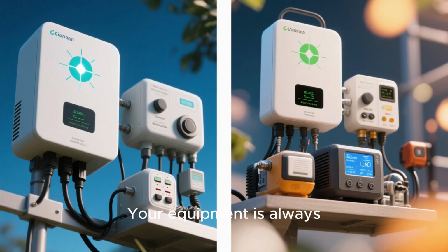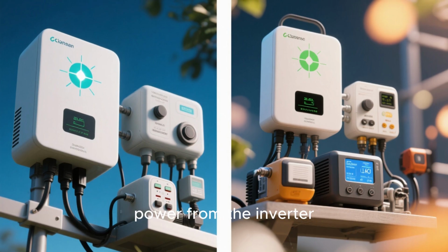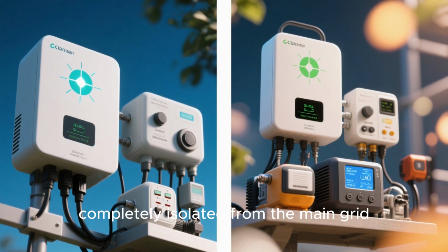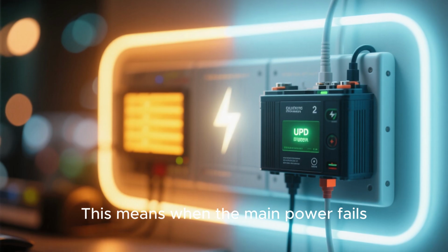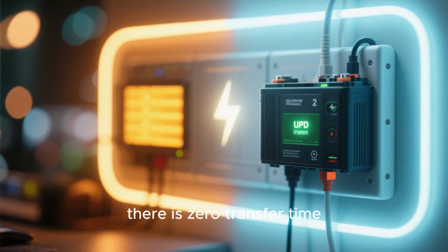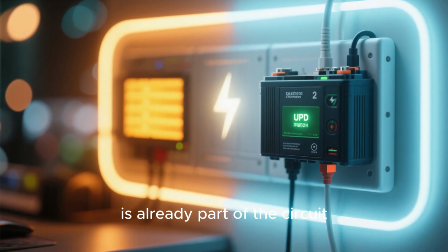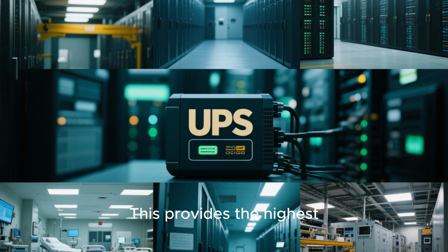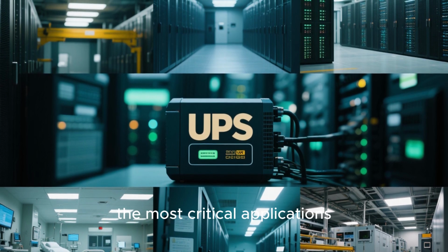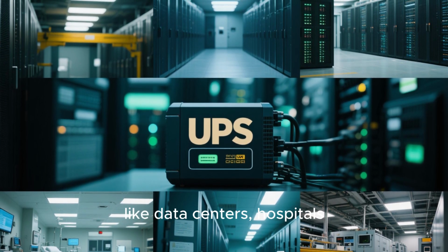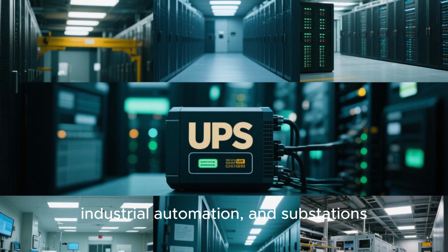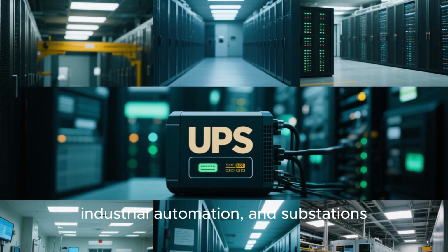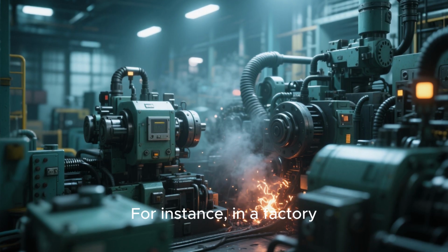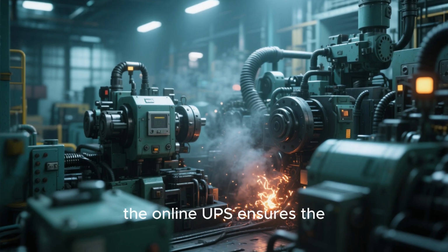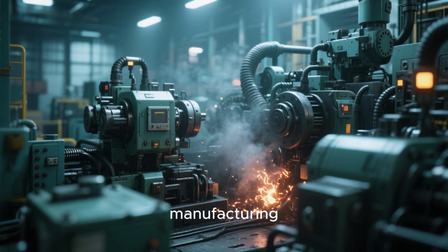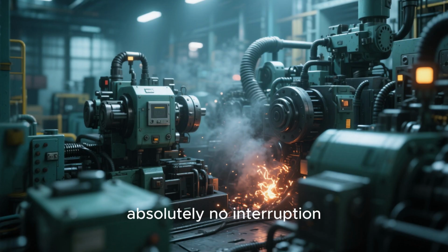Your equipment is always running on this perfectly recreated power from the inverter, completely isolated from the main grid. This means when the main power fails, there's zero transfer time. The battery is already part of the circuit. This provides the highest level of protection and is used in the most critical applications, like data centers, hospitals, industrial automation, and substations. For instance, in a factory, if the power fails, the online UPS ensures the manufacturing machines keep running with absolutely no interruption.